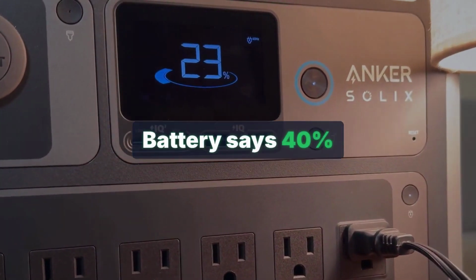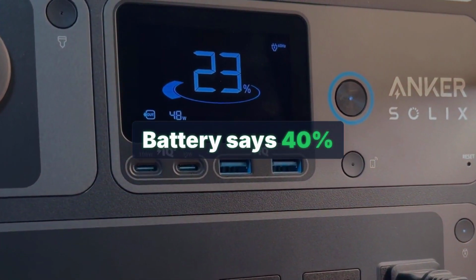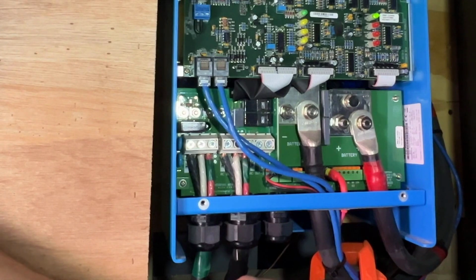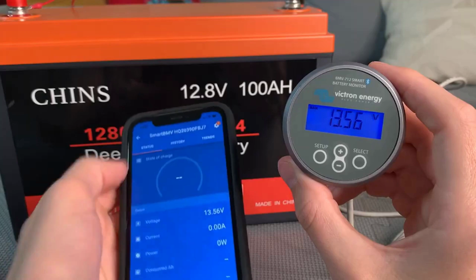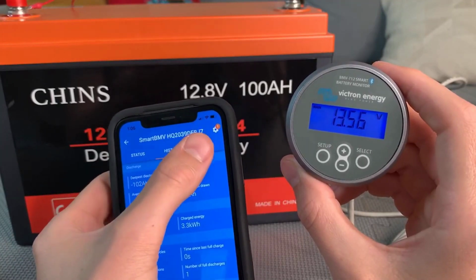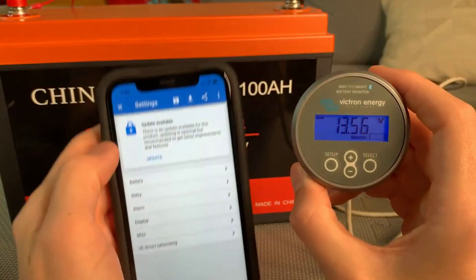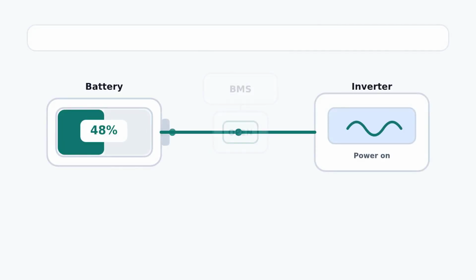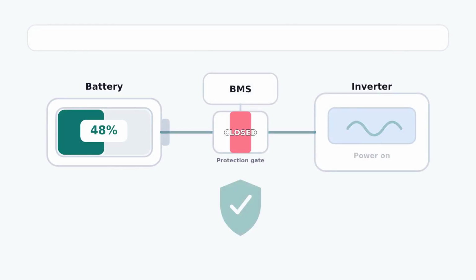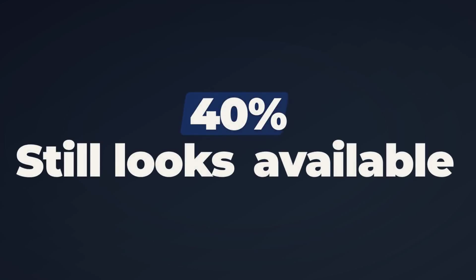The fridge is running, the inverter is humming, battery display says 40%. Then, nothing. Inverter drops. Loads go dark. You check the screen and it reads 40%, same as before it quit. That is not a glitch. That is the battery management system executing a controlled shutdown, and it chose to do it with nearly half the capacity still showing on the display.